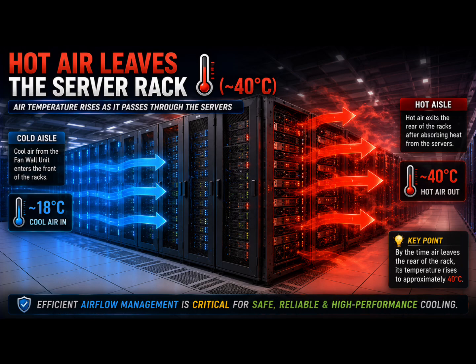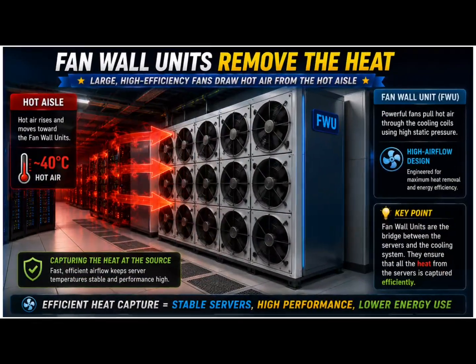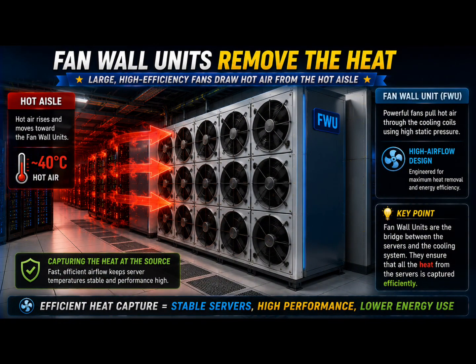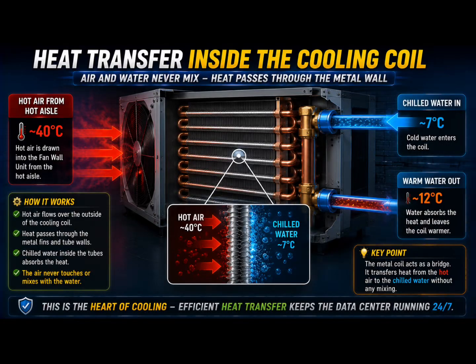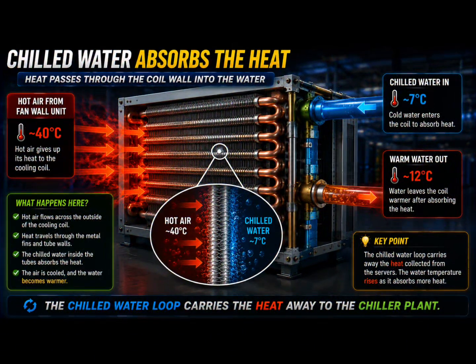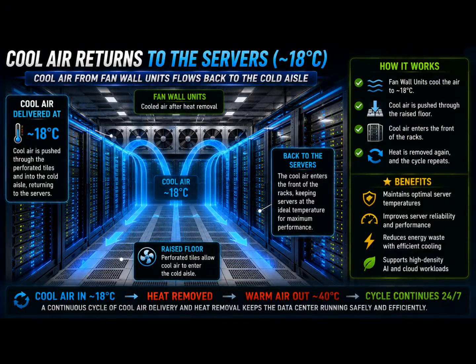Now, the fan wall units take over. Large, high-efficiency fans draw the hot air through chilled water cooling coils. Inside those coils, something remarkable happens. The air never mixes with the chilled water. Instead, the heat passes through the metal walls of the cooling coil. The chilled water absorbs the heat. The air temperature falls to approximately 18 degrees Celsius. That cooled air returns to the cold aisle.